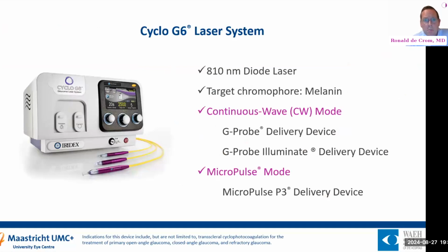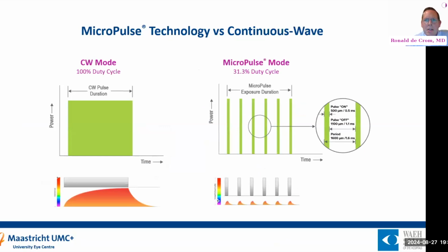And Thomas just mentioned the system in which you can perform both the continuous wave mode and the MicroPulse mode. And here again, you can see the difference between the two modes. So the continuous wave pulse with a long duration in comparison with the MicroPulse mode, in which the energy is on and off between the modes.